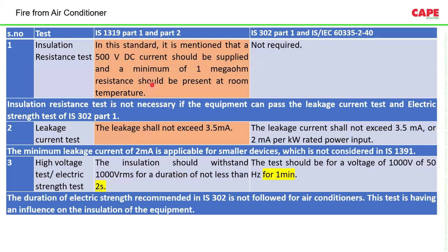We made a detailed study and we are trying to publish one report. For example, point number 3, the high voltage test, the electric strength test, is very, very important for an electrical appliance because most often failures are due to insulation failure. IS 1319 asks for a 1,000-volt test for 2 seconds. That means between the phase or the neutral conductor and the body, 1,000 volts is applied for 2 seconds and the equipment shall not fail.